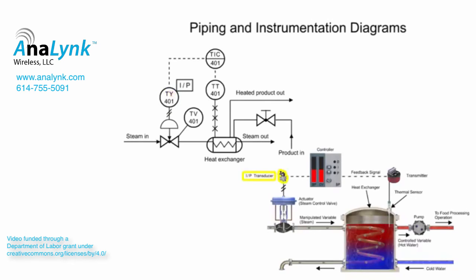The transducer converts an electronic signal to a pressure signal and is indicated by the square containing the letters I/P. The line with diagonal marks designates a pneumatic connection.